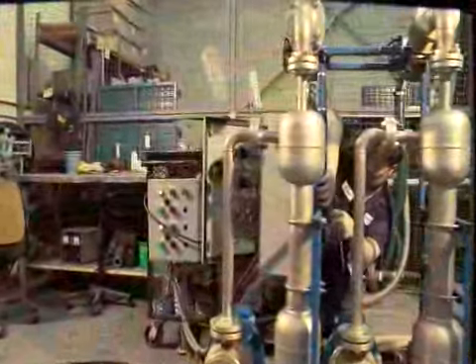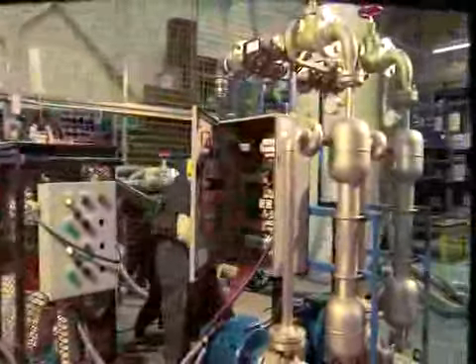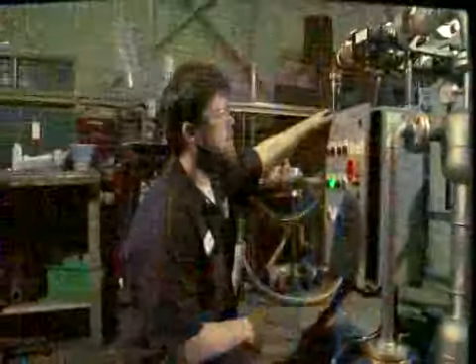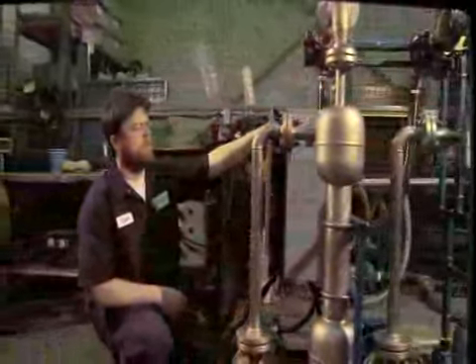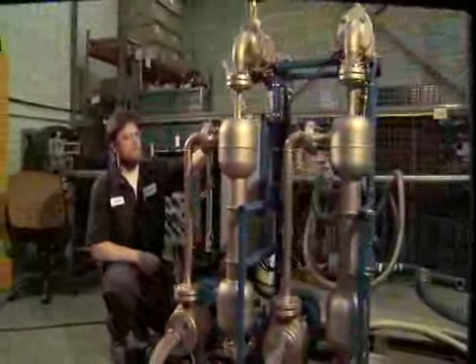Another clean water supply option is this self-contained water quality package built by the bearing and seal supplier. It operates on a different principle, using a hydrocyclone to separate abrasive particles greater than 80 microns from the water. This one has 2 separators and pumps for redundancy.